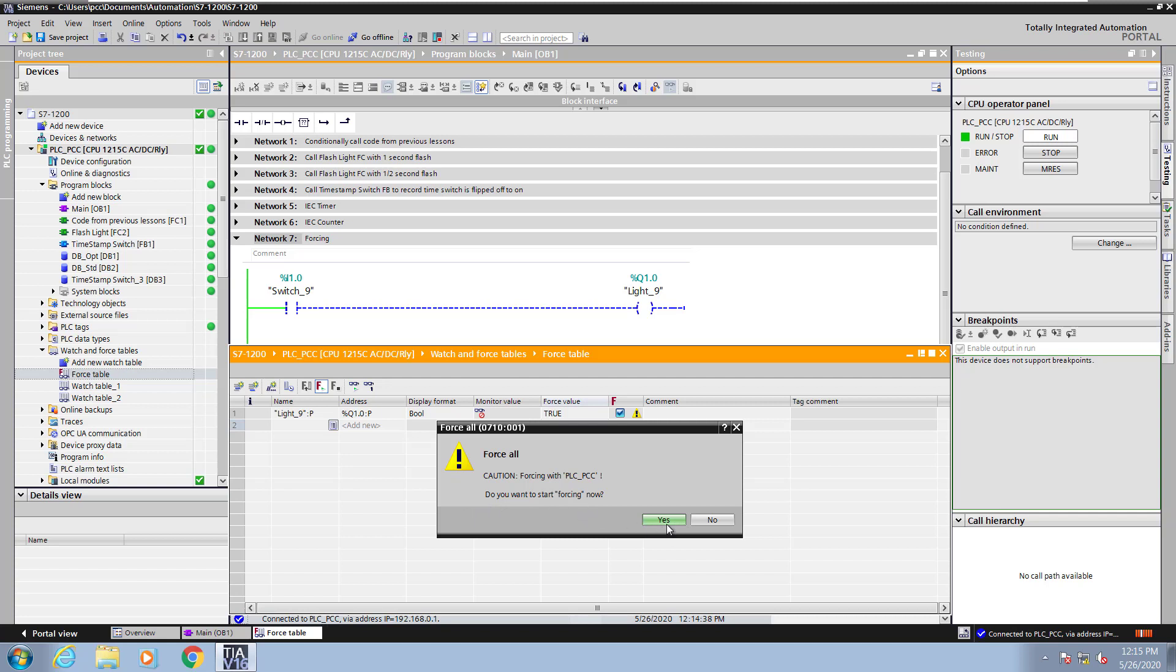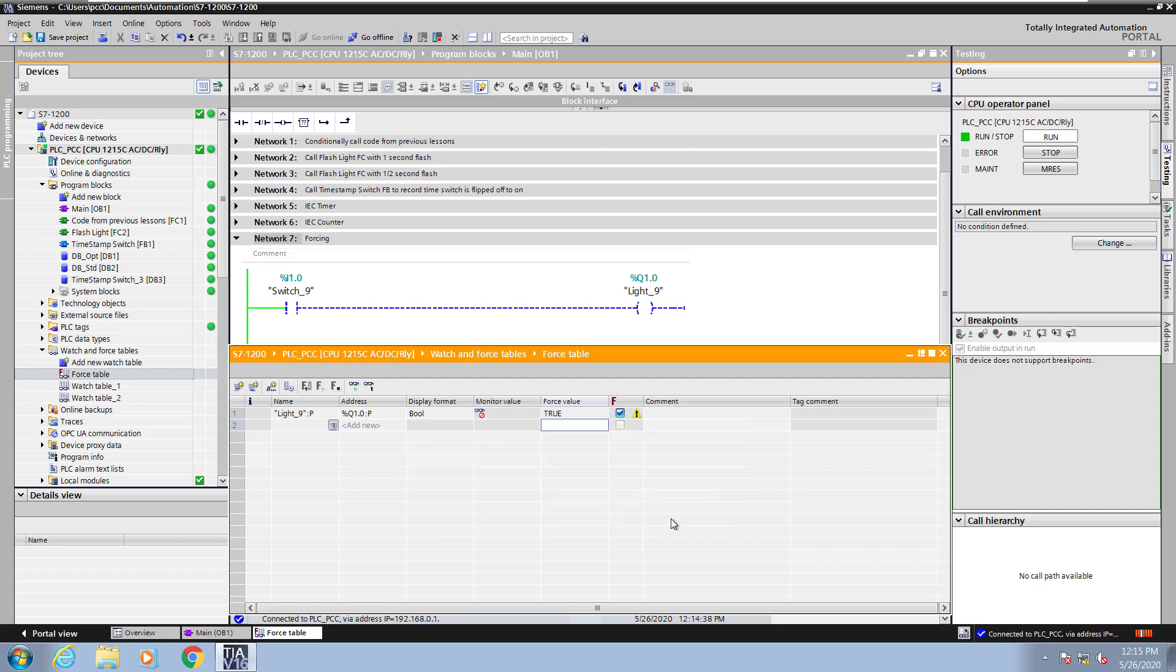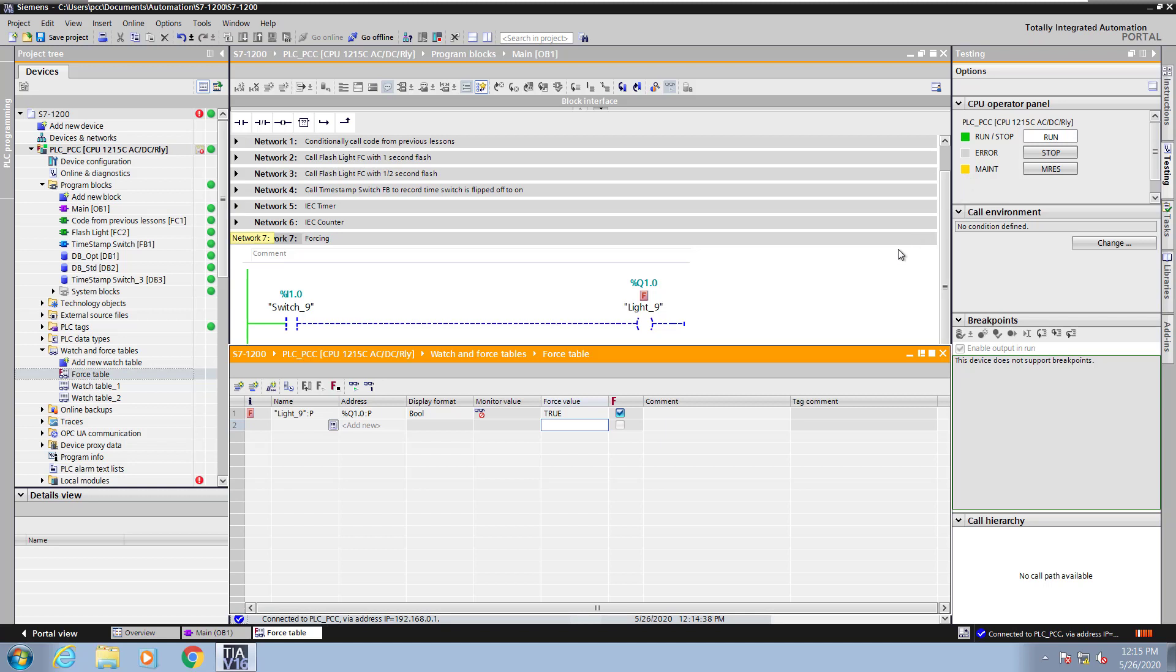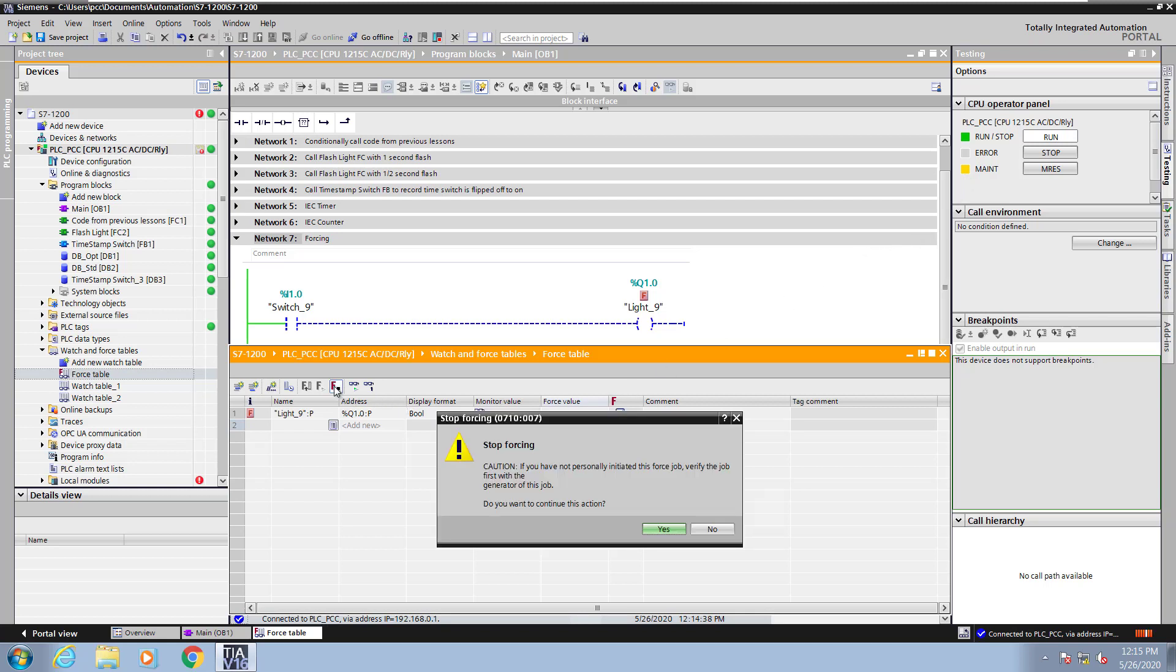When I select force all and say yes, the F above the light nine tag indicates that it is being forced, but you will not see the logic being updated because the value is written directly to the card. The yellow maintenance light does come on while you're forcing.